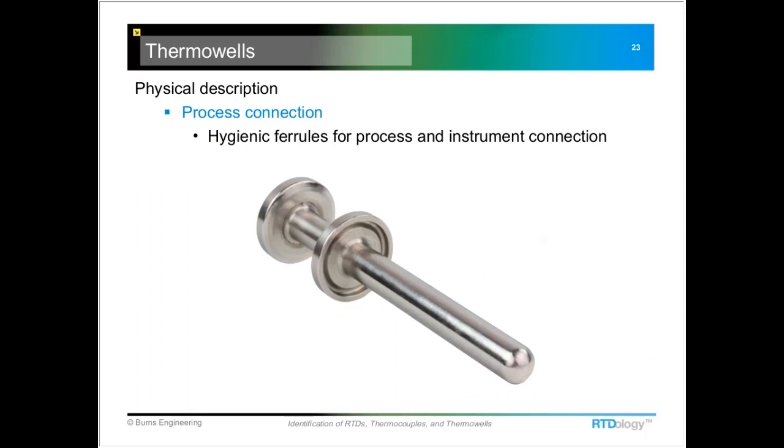This sanitary well has a hygienic ferrule for the process connection and also one for the instrument connection. This is important to note if you're trying to find a replacement temperature probe — it will need to have that hygienic ferrule on the temperature probe in order to mate up with this style thermowell.